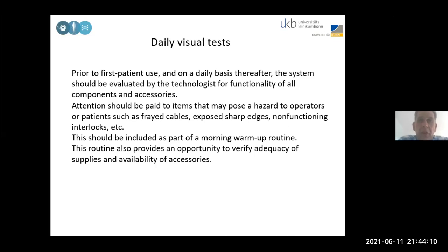What do you do on quality control if you enter the room on a daily basis? The first thing I usually do if I'm entering the X-ray room and patient treatment has not started so far, you should actually have a view on your machine. Sometimes somebody has been in the room after you have done the last patient on the last day, and you should check what had happened there. And look that the warm-up procedure is written down so that everybody could do the warm-up procedure. Everybody is introduced to the warm-up procedure. And please check what is in the warm-up procedure. What are the properties and the parameters that need to be checked.